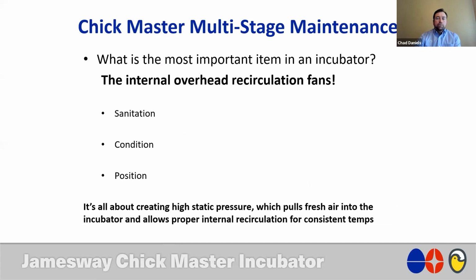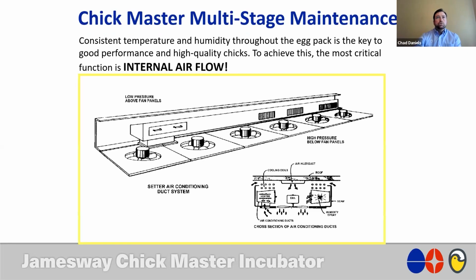And the thing that we're trying to accomplish with these fans is, if everything is in great shape, it's all about creating high static pressure. So this pressure that's created as the fan operates is what pulls fresh air into the incubator and allows proper internal recirculation for consistent temperatures. And so that's what we have to keep in mind. Unfortunately, the fan is what comes in contact with the air being pulled in and the recirculation, so it has an opportunity to also get damaged or to get dirty or to be not in the proper position. So let's work through a few of those details.